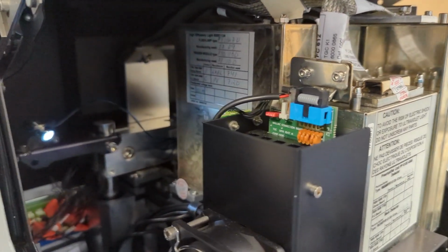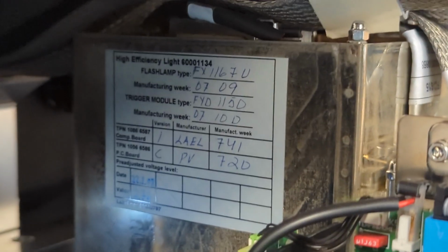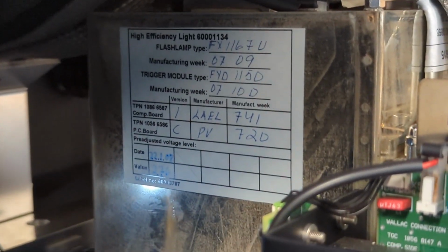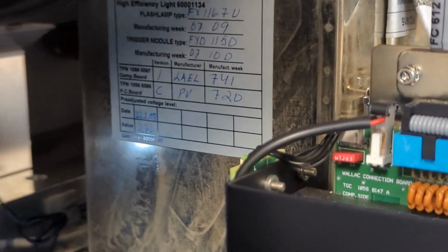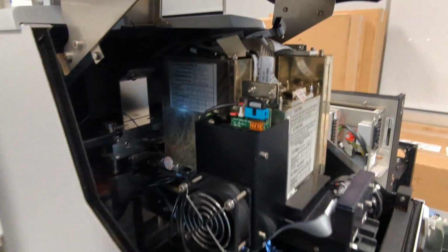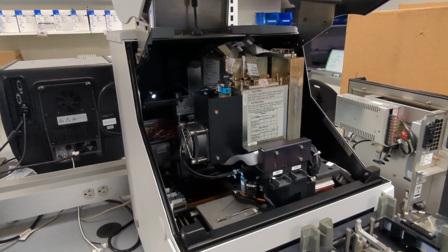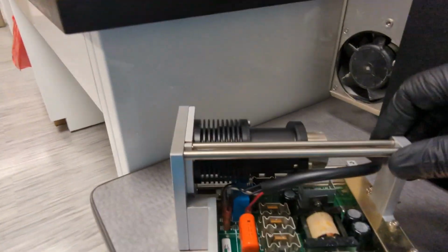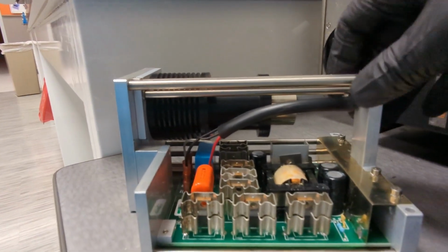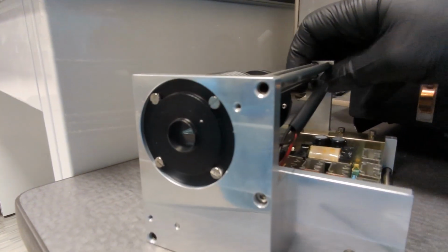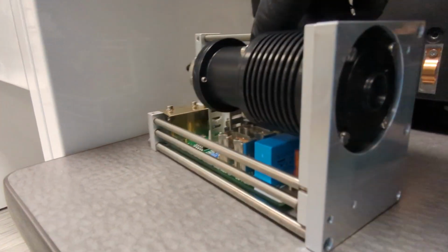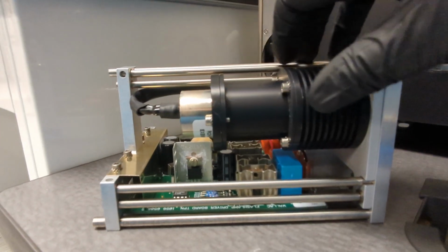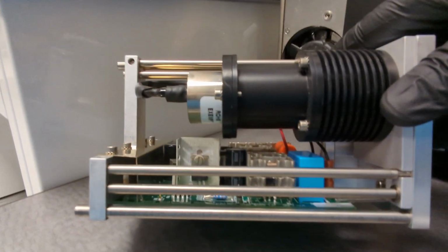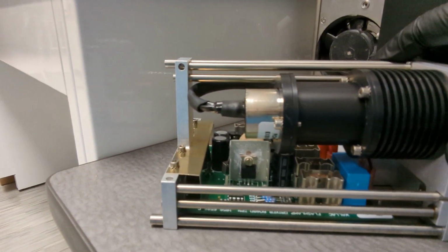And as I said, this is a xenon flash lamp, and so you can see that right there. These types of lamps are pretty common in spectrophotometers and plate readers. They require a high voltage, and so thanks to our parts unit, I actually have one of the light sources to one of these right here with the case off, and you can see this is the xenon lamp. It's a big lamp, and I don't see a make and model on it. This just says RoHS exempt, so that's not having anything to do with it.